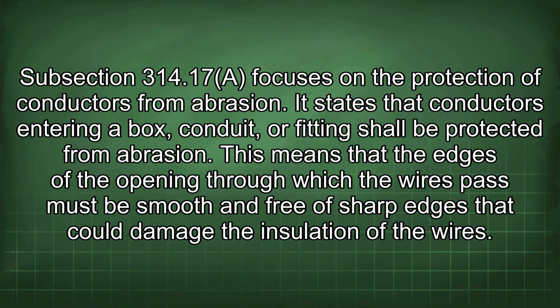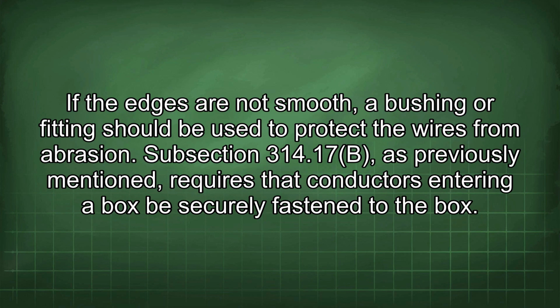Subsection 314.17 focuses on the protection of conductors from abrasion. It states that conductors entering a box, conduit, or fitting shall be protected from abrasion. This means that the edges of the opening through which the wires pass must be smooth and free of sharp edges that could damage the insulation of the wires. If the edges are not smooth, a bushing or fitting should be used to protect the wires from abrasion.